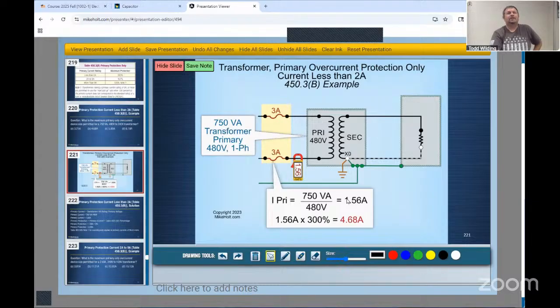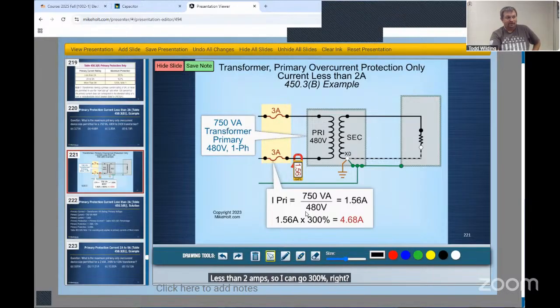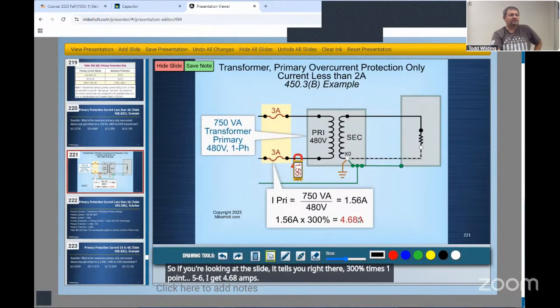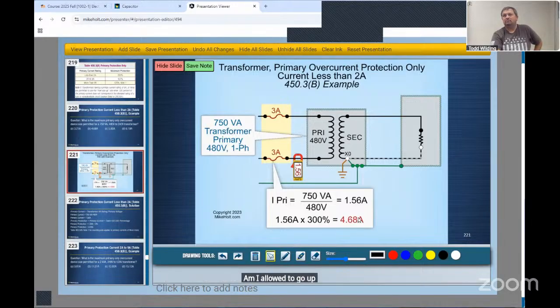300 less than 2 amps, so I can go 300%, right? So if you're looking at the slide, it tells you right there, 300% times 1.56, I get 4.68 amps. Am I allowed to go up or down? Less than 2 amps is what the thing said, right?